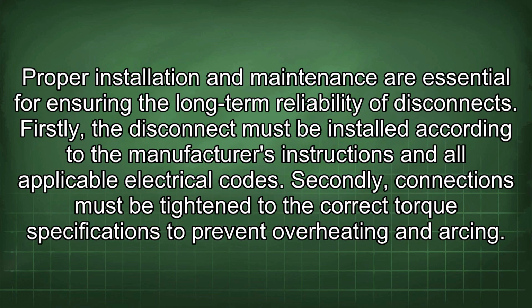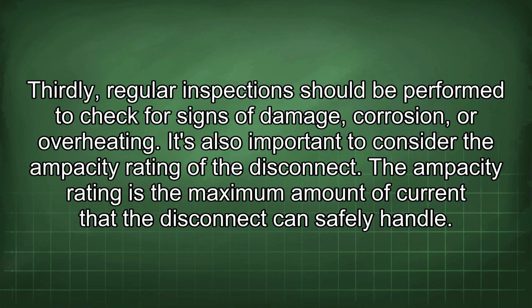Proper installation and maintenance are essential for ensuring the long-term reliability of disconnects. Firstly, the disconnect must be installed according to the manufacturer's instructions and all applicable electrical codes. Secondly, connections must be tightened to the correct torque specifications to prevent overheating and arcing. Thirdly, regular inspection should be performed to check for signs of damage, corrosion, or overheating.